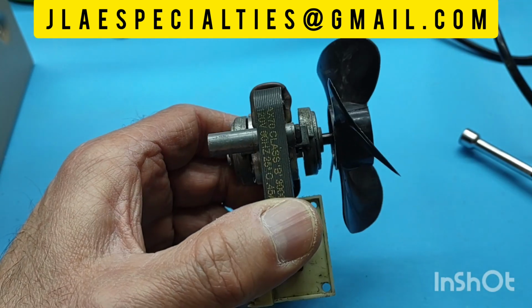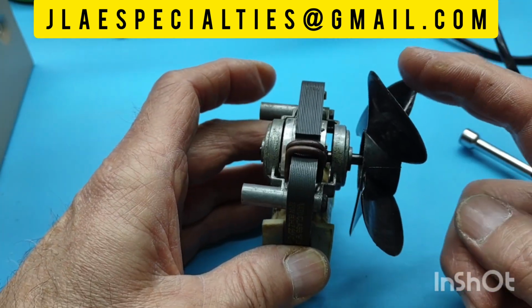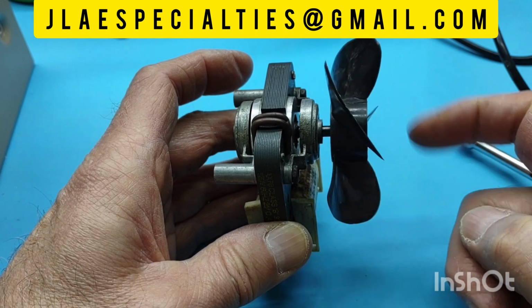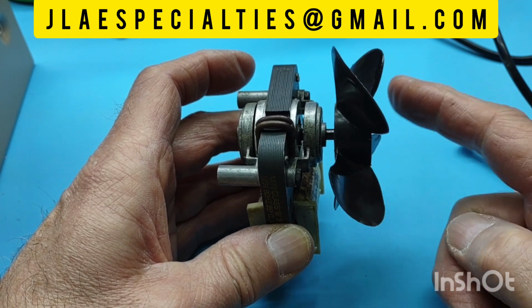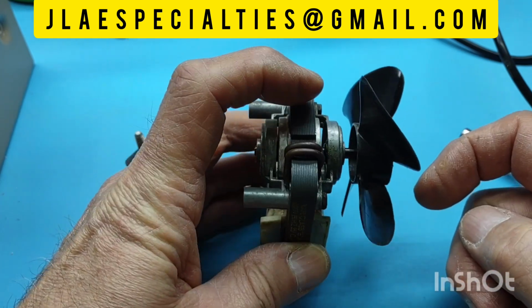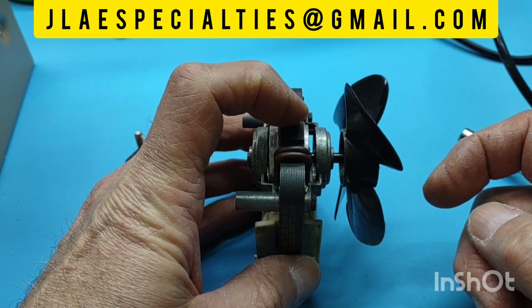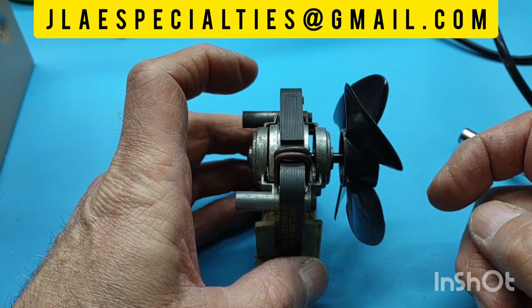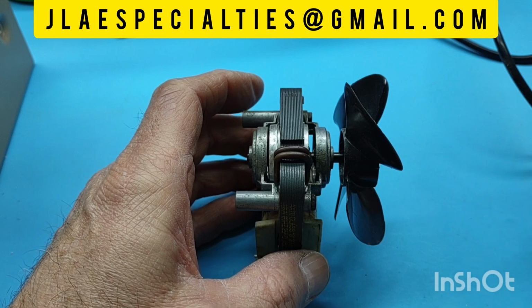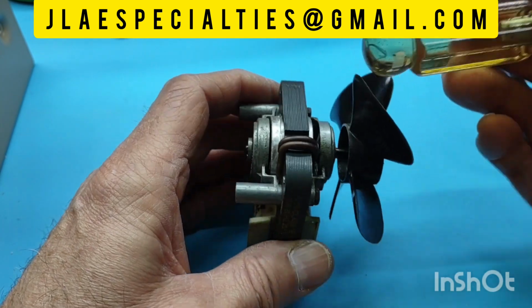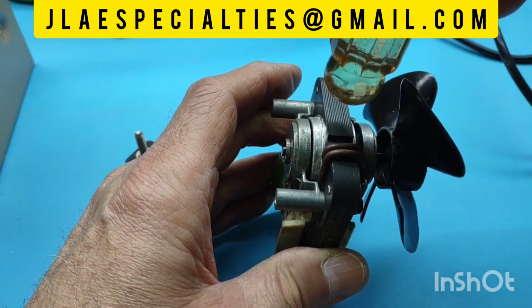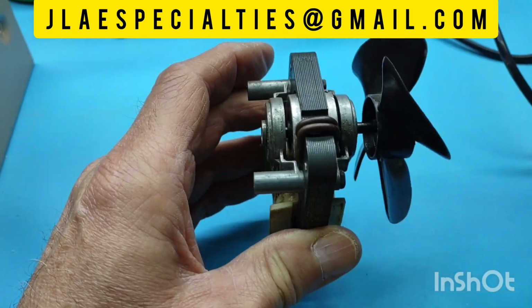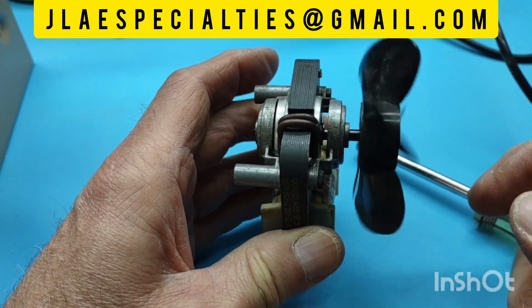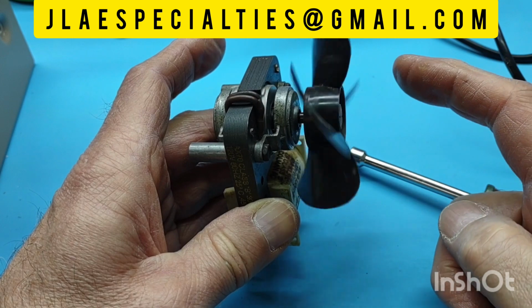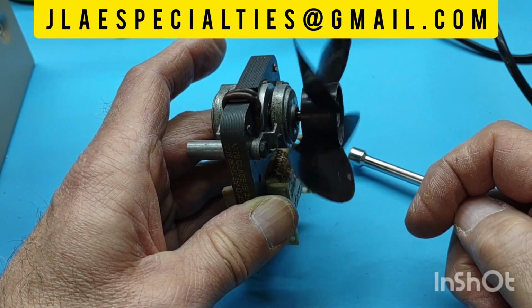This fan motor's back together, and as I mentioned before, it doesn't spin freely. So the solution to this is to tap on the housing, right here. You don't want to hit it with a hammer -- you can use the back of a screwdriver -- and you tap on that, and now the fan spins totally free.